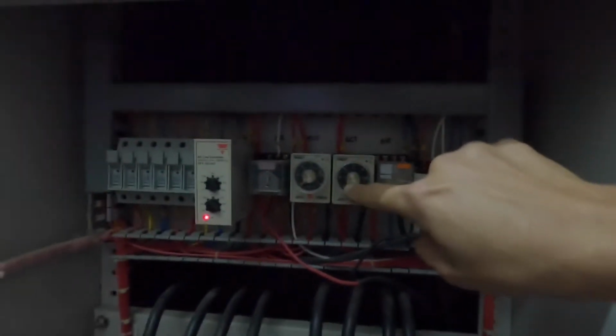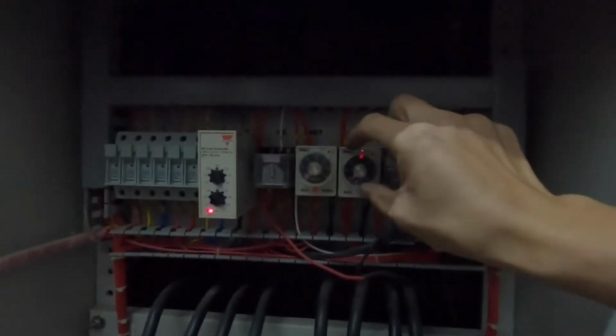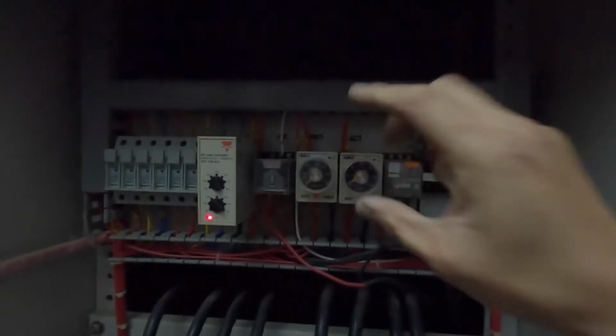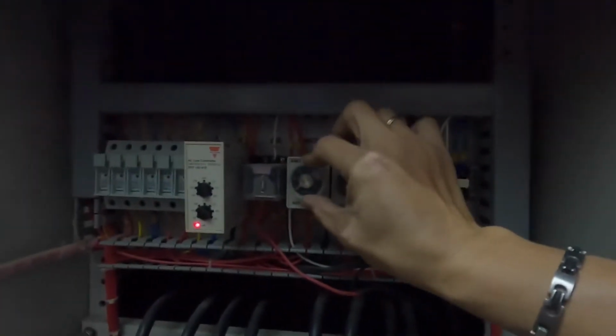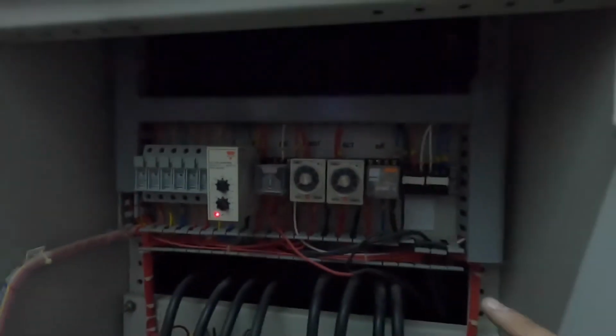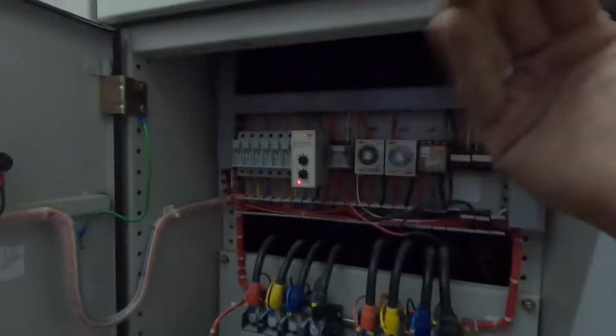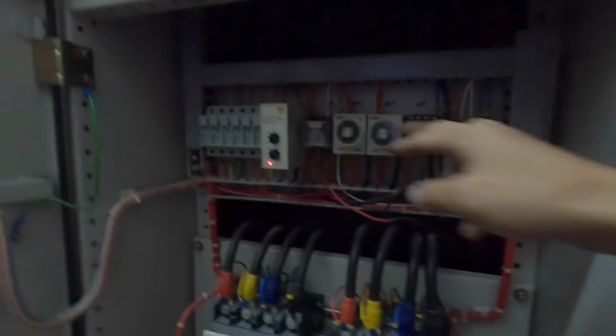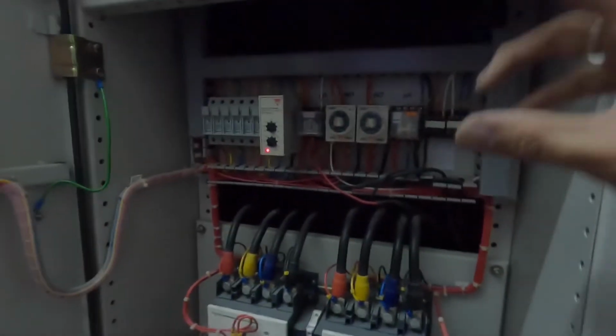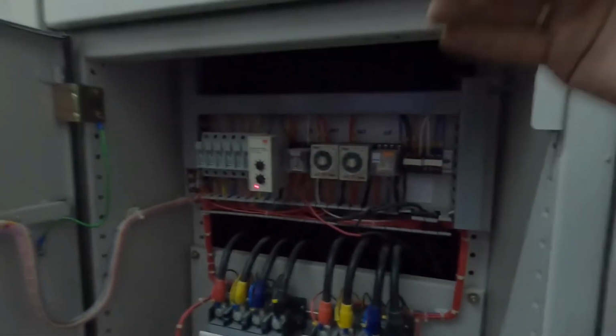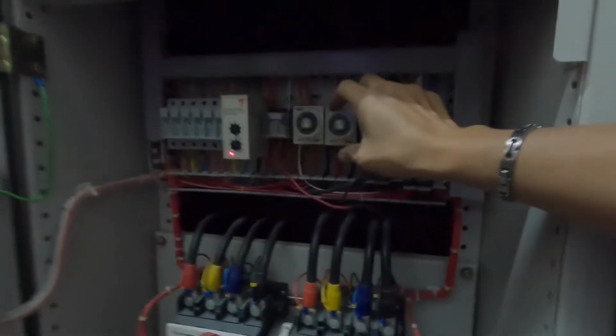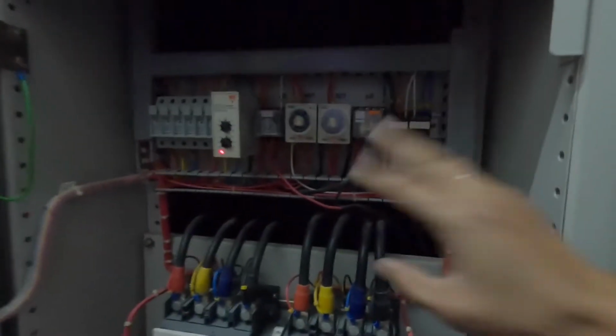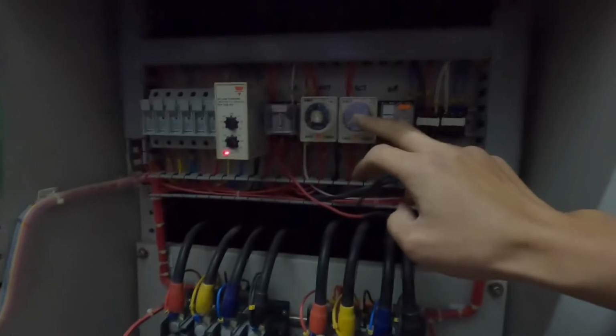Alright, and also this timer relay is set to too fast. Cannot be too fast. Must have some delay, at least 2 or 3 seconds. Okay, cannot be too fast. Too fast, before the genset voltage stable, you sudah change over. Frequency tak stable, sudah change over, barang senang rosak. Delay for 2 to 3 seconds. Not too long macam ni okay. 2 to 3 second delay, not recommended to be instantaneous.